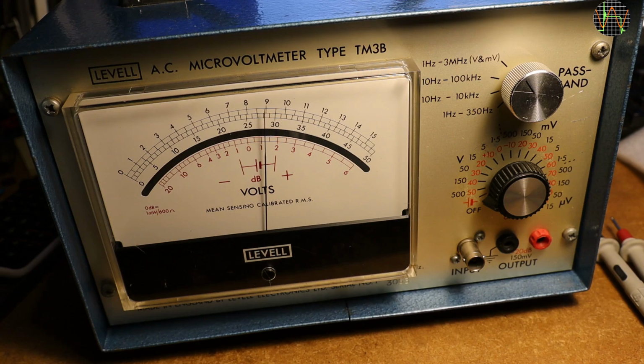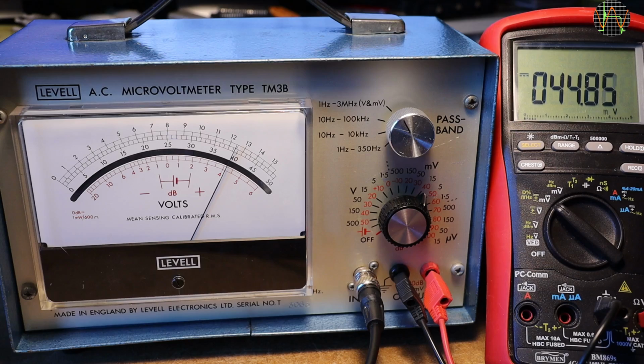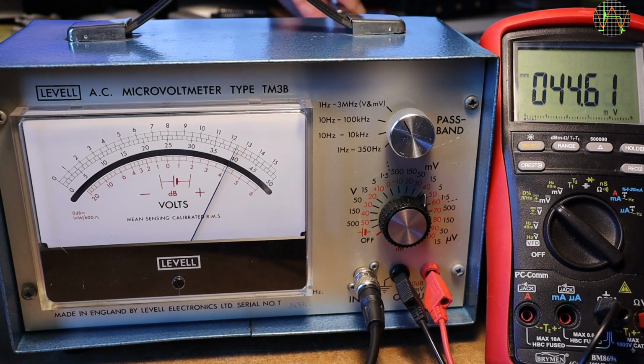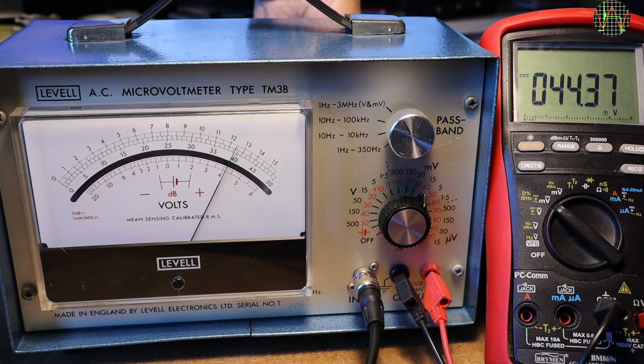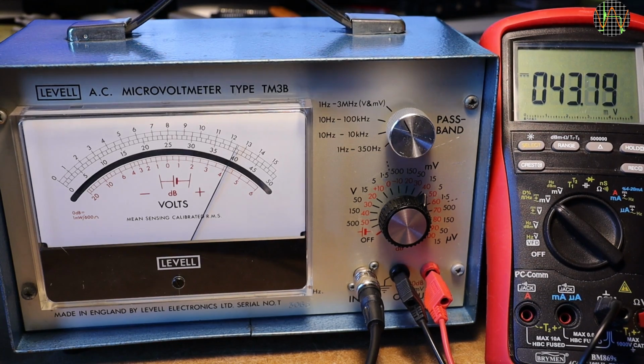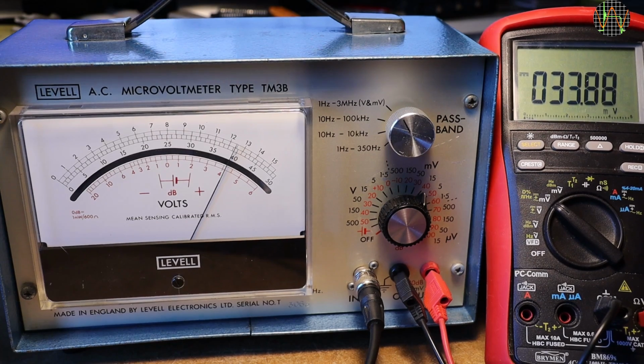With that done, onwards to calibration. With 12.5 millivolts at 1 kHz in the 15 millivolts range, the DC offset on the output terminals should be less than 50 millivolts. With about 45 millivolts it is, but it does not hurt trying to reduce it further, and by adjusting the bias trim pot in the rear I managed to reduce it down to about 34 millivolts.